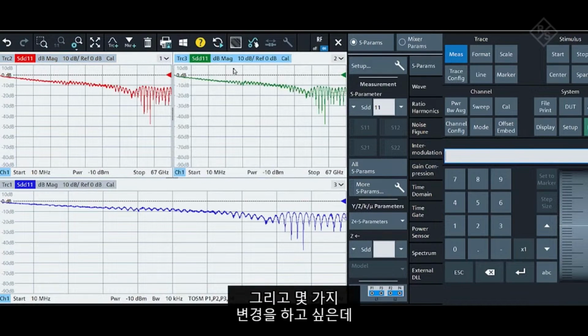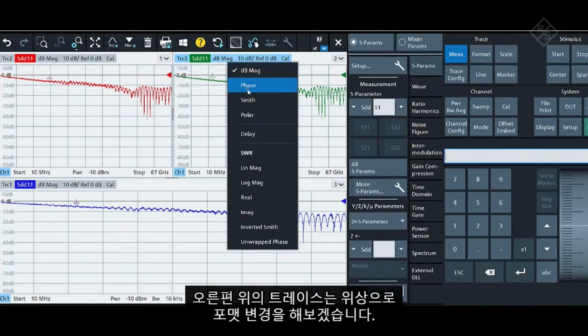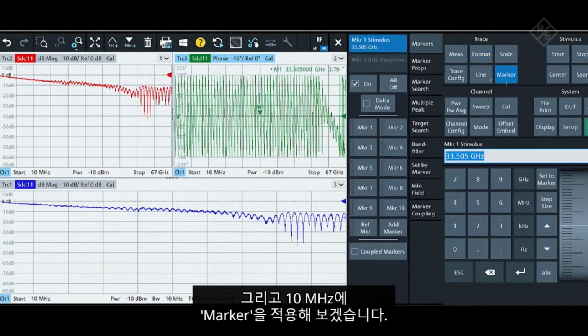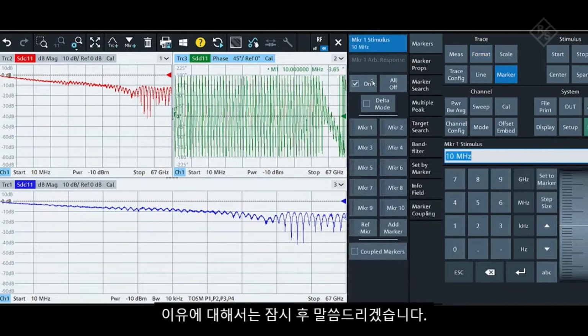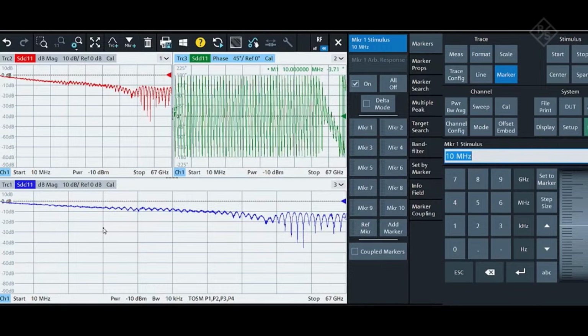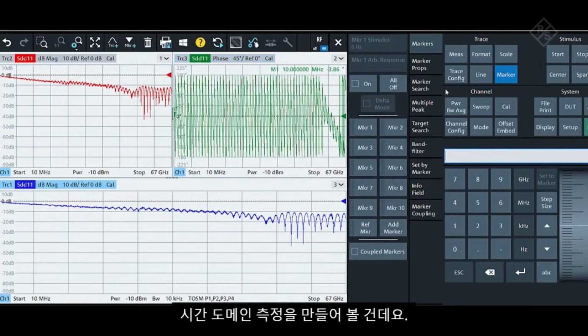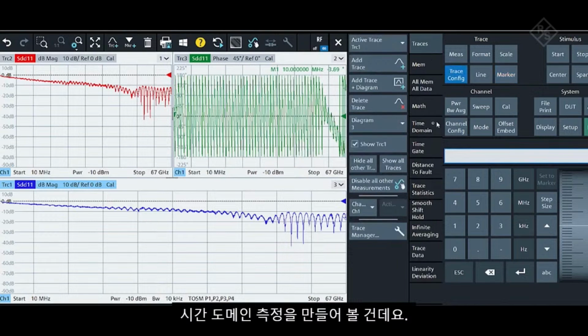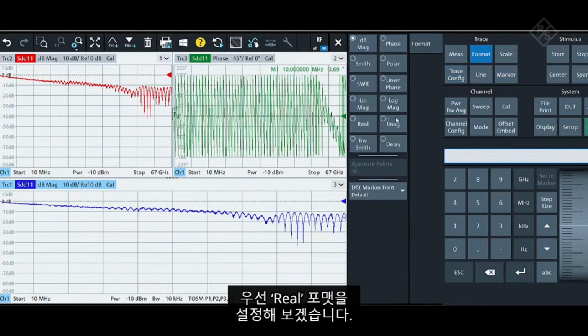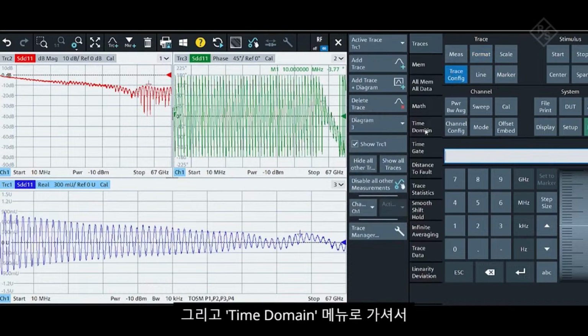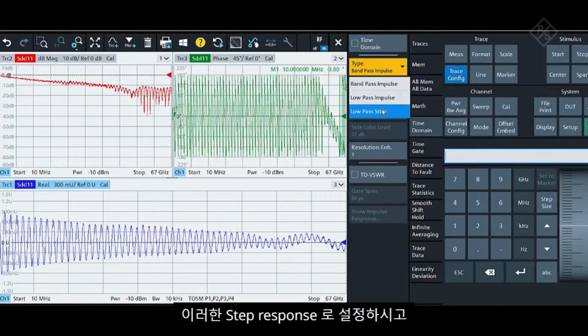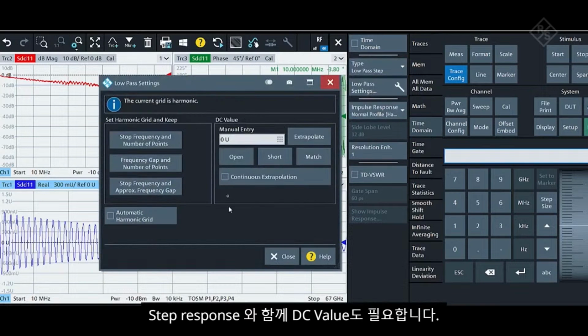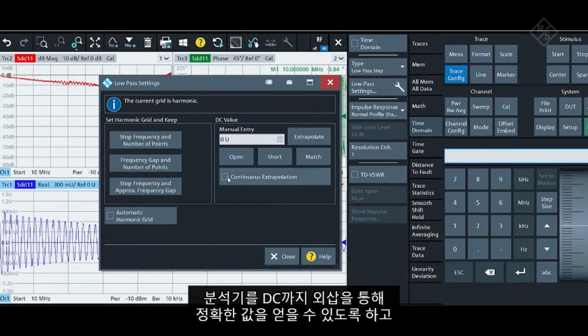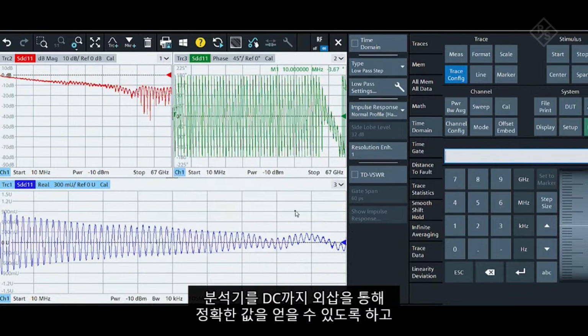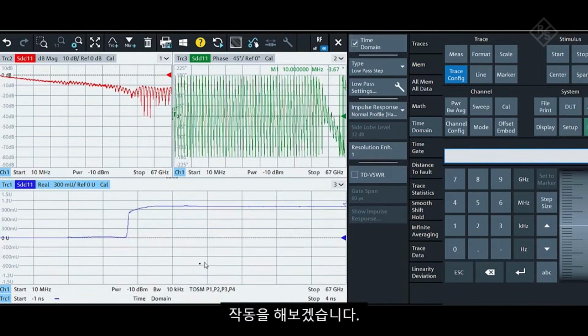And I'll make a couple changes here. I'm going to change the format of this one in the upper right to phase, and I'm going to put a marker at 10 megahertz. I'll explain why in a second. And down here, I want to make this a time domain measurement. First let's set our format to be real. Then we can go into our time domain menu and make this a step response. With the step response, we need a DC value. We can let the analyzer extrapolate down to DC so we get an accurate value. And then let's turn this on.